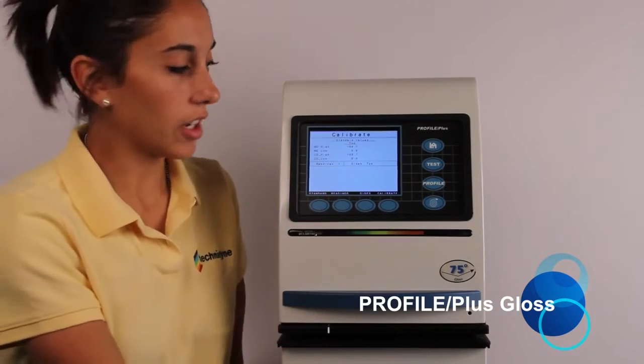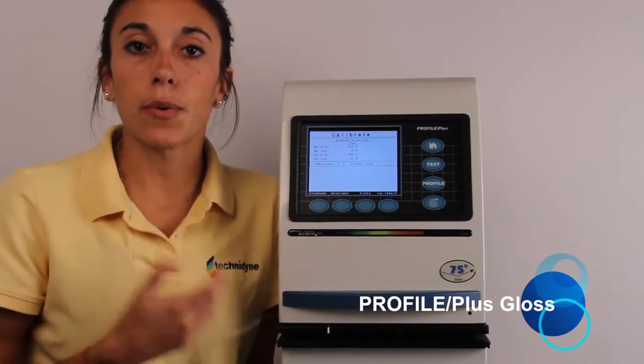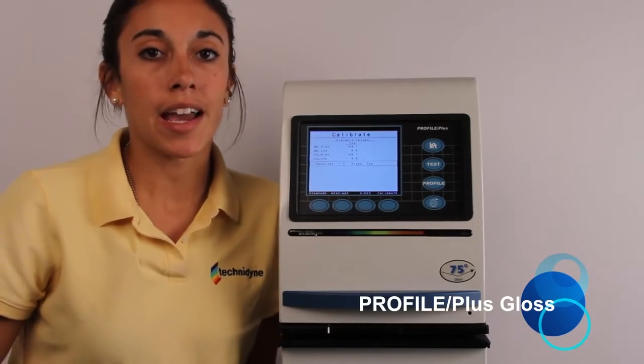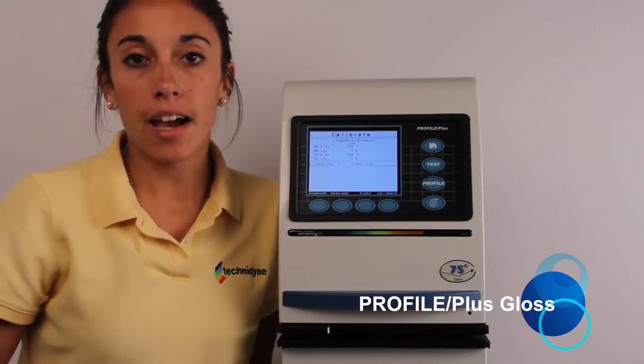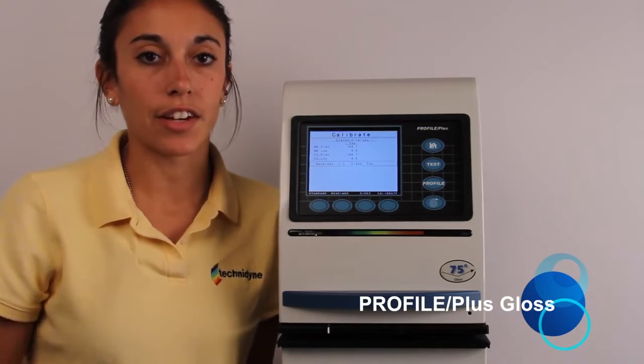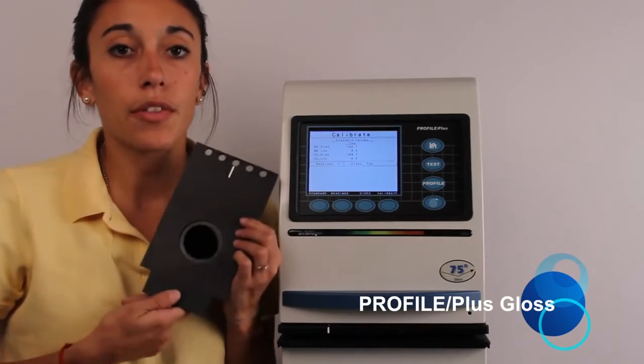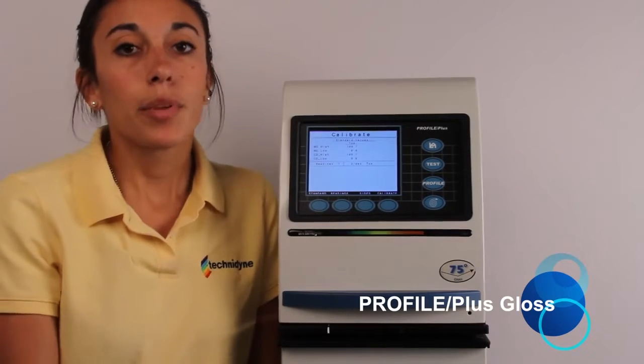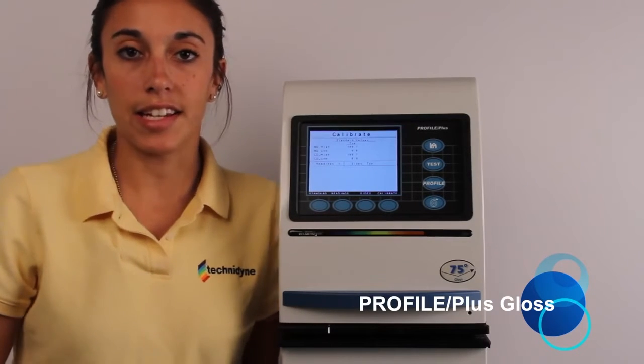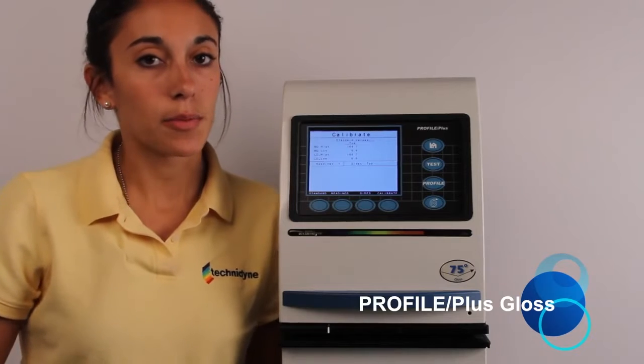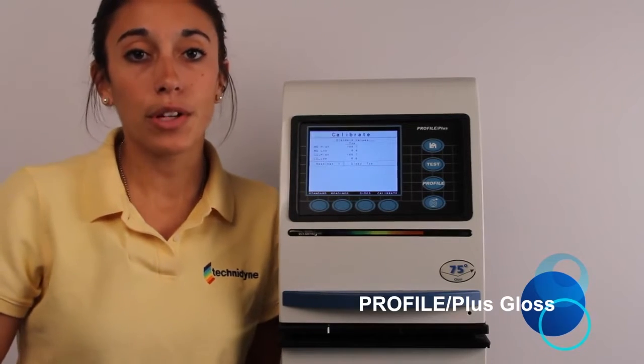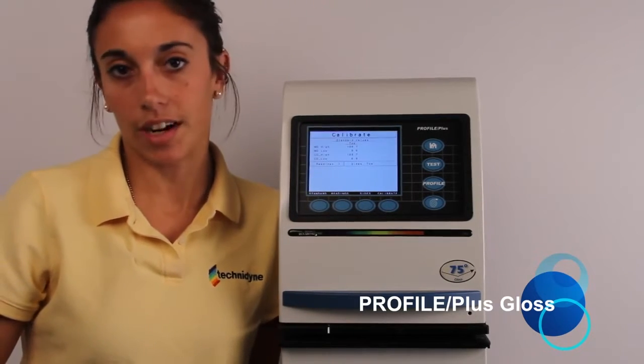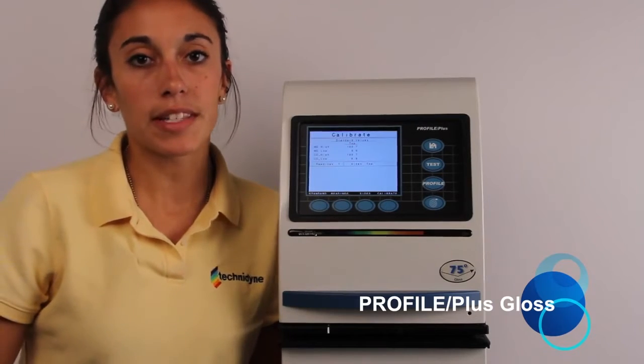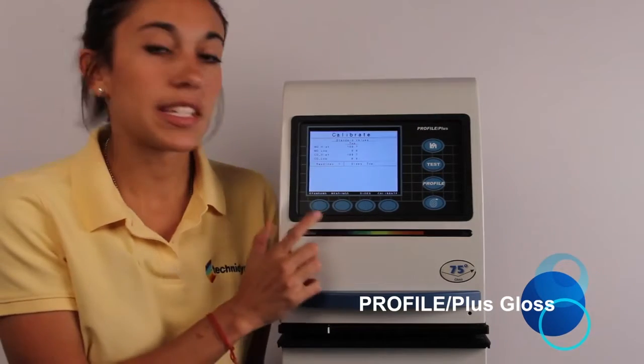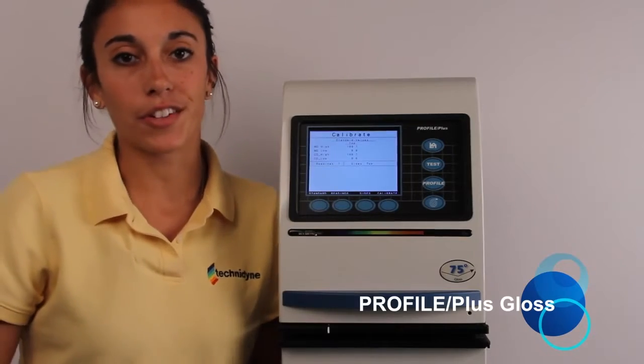Now if you look on the screen, you should see MD, which stands for machine direction. There should be an MD high and an MD low. For the MD high, we're going to use our 100.7 standard, and for the MD low, we'll use our other standard as our 0 point. Below that, you should see CD high and CD low. CD stands for cross machine direction, and once again for the high we'll use 100.7 and for the low we'll use 0. If you need to make any adjustments to any of the values, you can press the standard soft key and just follow the on-screen instructions.